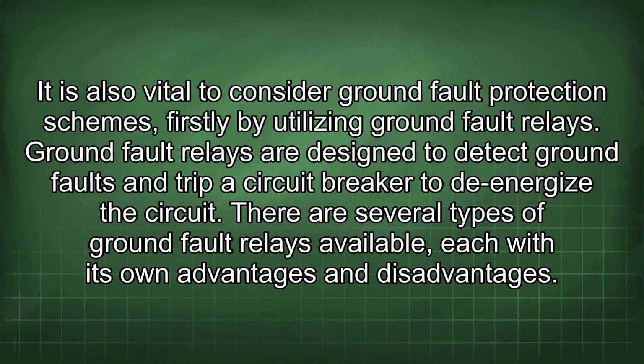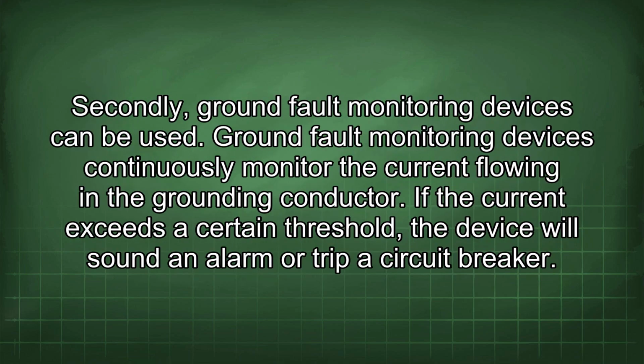Ground fault relays are designed to detect ground faults and trip a circuit breaker to de-energize the circuit. There are several types of ground fault relays available, each with its own advantages and disadvantages. Secondly, ground fault monitoring devices can be used. Ground fault monitoring devices continuously monitor the current flowing in the grounding conductor. If the current exceeds a certain threshold, the device will sound an alarm or trip a circuit breaker.